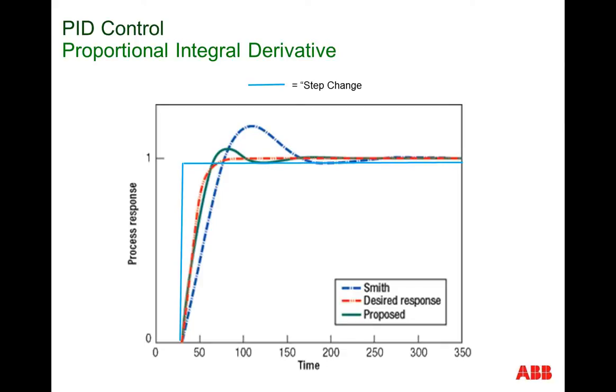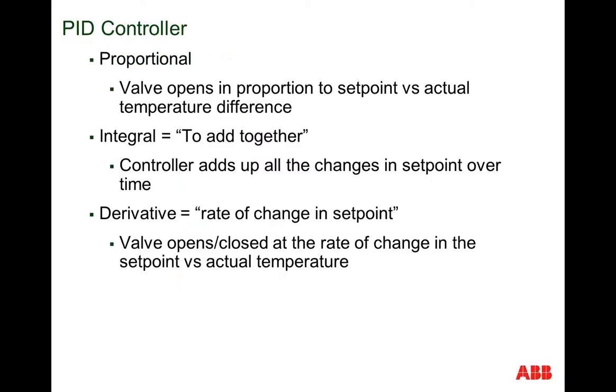Now, here's why you need calculus. Let's say you suddenly crank up a set point from 0 to 100%, shown by the light blue line. The system will open the gas valve at full bore and heat the chemicals as fast as possible. But there is a possibility, based upon the design of the system, that once the temperature crosses the set point line, there will be a delay in closing that valve, and thus overshoot, as shown by the dark blue and the green lines. We want a system that's smart enough to start backing down the gas valve when we come close to set point, as shown by the desired red line.